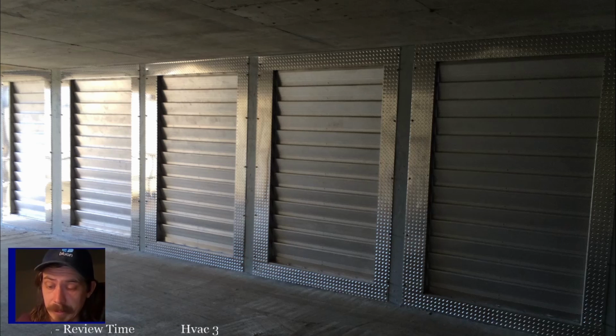ECM motors sequentially energize the windings to provide rotation. Like I said, it's basically a 3-phase motor and set up just like a 3-phase motor. So it sequentially powers those windings to get the motor operating. Instead of having a start and a run winding, which dictates that motor rotation, it actually powers windings at different times, and that's what makes the motor rotate. You have a north and south magnet on the rotor, and as the winding energizes, it attracts that magnet and it causes rotation. So sequential energizing of ECM motor windings provides rotation of the rotor. That is also in section 6.1. And then what does the presence of 4-pin connections on an ECM signify?